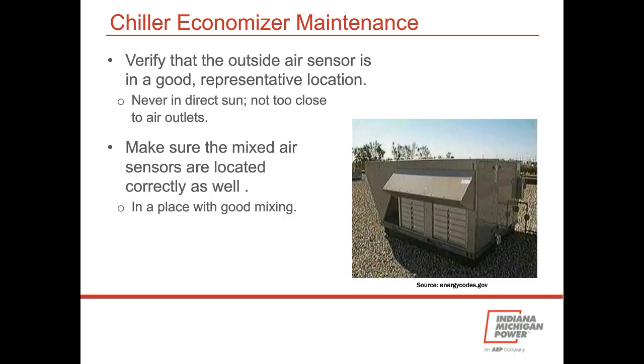It's important for economizers where your air sensors are located. You don't want them directly in the sun or too close to other air outlets. And when you're looking at mixed air, typically you're measuring the return air along with the incoming supply air, and you want that in a place that has good mixing as well.